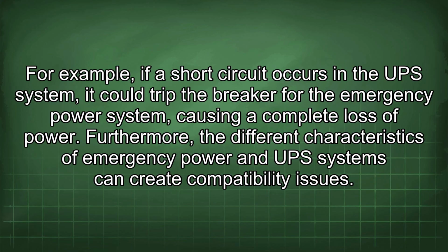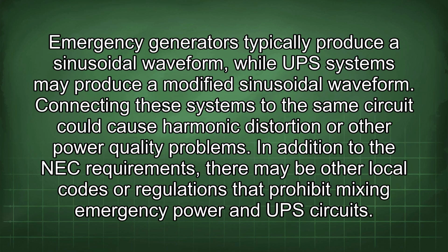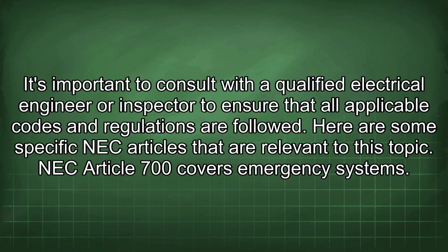Furthermore, the different characteristics of emergency power and UPS systems can create compatibility issues. Emergency generators typically produce a sinusoidal waveform, while UPS systems may produce a modified sinusoidal waveform. Connecting these systems to the same circuit could cause harmonic distortion or other power quality problems. In addition to the NEC requirements, there may be other local codes or regulations that prohibit mixing emergency power and UPS circuits. It's important to consult with a qualified electrical engineer or inspector to ensure that all applicable codes and regulations are followed. Here are some specific NEC articles that are relevant to this topic.